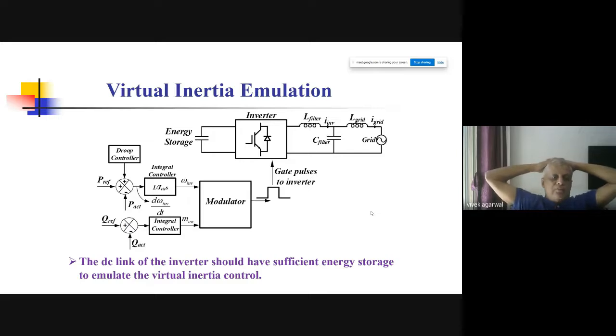The same applies at the bottom, which is the loop that corrects the voltage. If there is a shortfall and voltage is falling on the grid, you supply reactive power and try to shore up the voltage, so it stabilizes back to the original value.